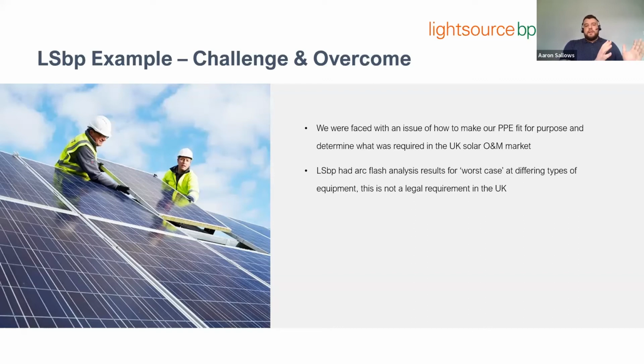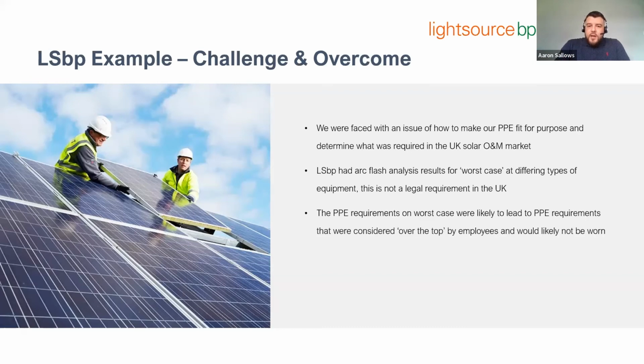But we did have some arc flash analysis, and it gave us the worst case values we'd be facing with certain types of electrical equipment through a grid-connected solar PV plant - HV to LV transformers, LVAC, LVDC, whether at inverters or combiner boxes. When we looked at the categories of PPE to fully mitigate the arc flash levels at all these types of equipment, we had conversations with working groups and people within the organization about what level of PPE would be required. The feedback we received, plus internal discussions, showed that if we imposed PPE to cover the worst case incident energy values, the likelihood is employees would not actually wear it.